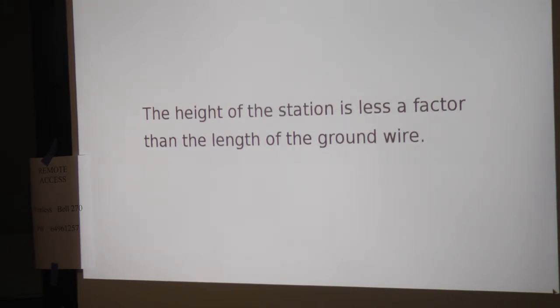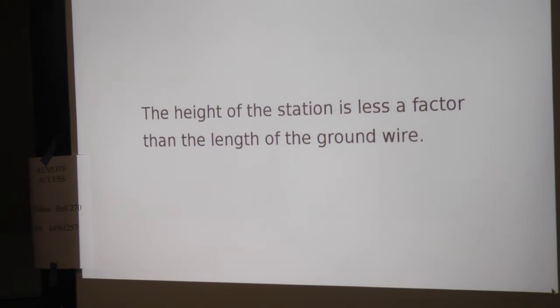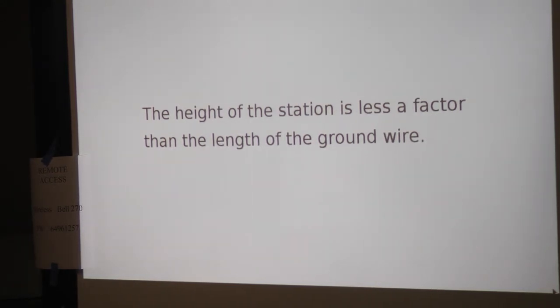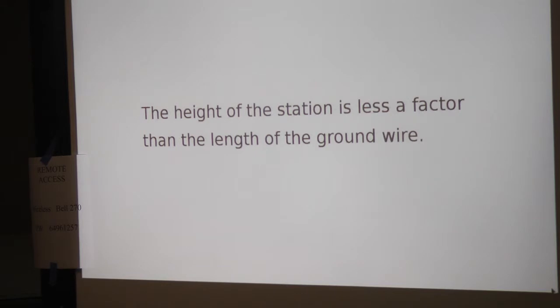Well, no, because it would act as one long ground. Yes, well, it would act as one long ground? The grounding plate has to be underground. Well, it's still second floor. Yeah, I know, absolutely, but can you not use that? No, it's like for the entire system - you already got a ground, it's already on the ground. The idea is to get the best possible ground, it needs to be short. It's not gonna be short if you're on the second floor. If your ground's there, putting another one there is not gonna do anything unless you do it separately.